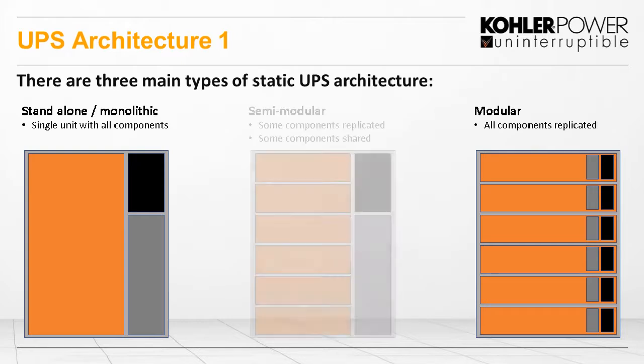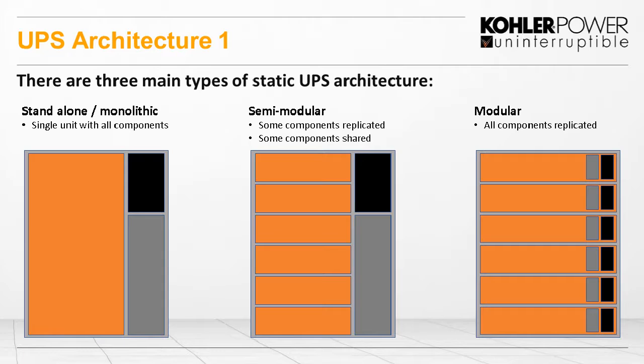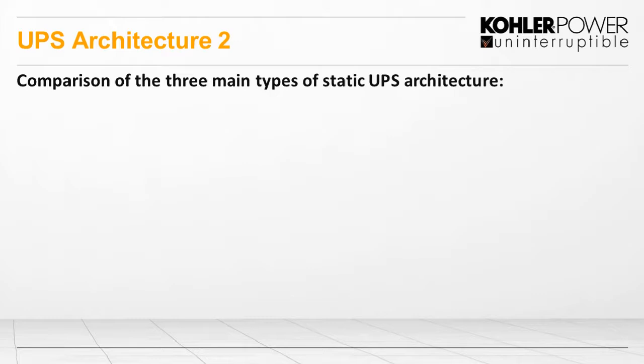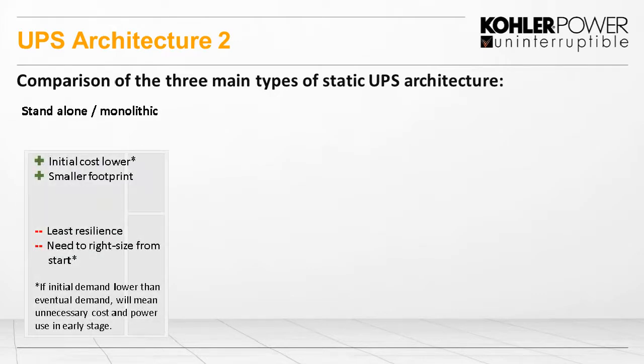Somewhere in the middle of this we have a bit of a hybrid which we call semi-modular, and this is where some components are replicated, some components are shared, and it can be a single or a multi, and it depends on which way you look at it. So we look at the comparisons of these, and the standalone. Now this is initially a lower cost because you're buying one component of each one. Can be smaller, but if it's just one standalone UPS, it's got a low resilience. You have to right size from the start, so you have to put a UPS in that has the required power for your final load demand that you're designing around.